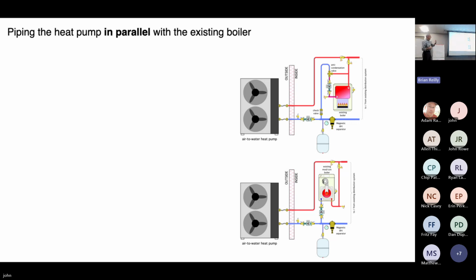You're adding the heat pump, and now you might choose to use outdoor reset control on the system. That's going to lower those water temperatures under partial load conditions. And we've seen this happen. The boiler that's operated fine for 10 or 15 years, all of a sudden, now it's being exposed to these lower water temperatures. And if it gets below 130, you're going to start to generate condensate inside the boiler.